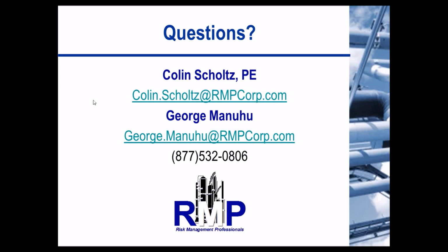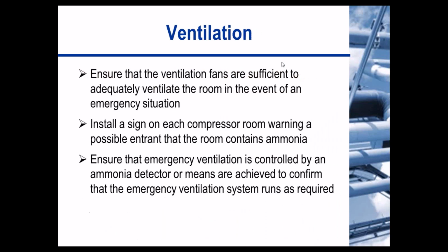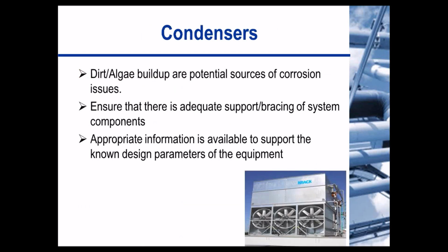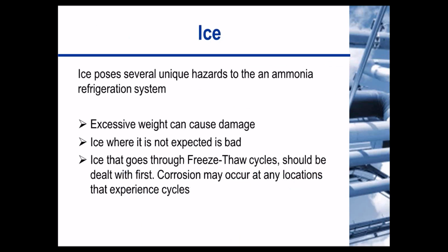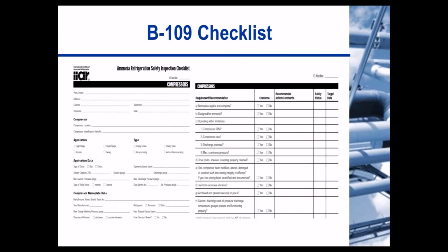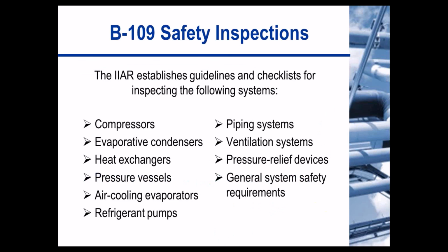Is there a requirement to have an outside contractor conduct the B109? Why don't you take this one? Sure. So the question was, is there a requirement for an outside contractor to conduct the 5-year inspection for the B109? Can we jump around in our slideshow a little bit? Well, in the B109, in the last paragraph before you get to the actual checklists, under frequencies of inspections, it mentions that you have to do annual visual inspections, and then every fifth year, a more thorough inspection must be completed by a qualified refrigerant engineer, fire safety authority, or other competent person. So that's what's spelled out in the standard, and that's open to interpretation.